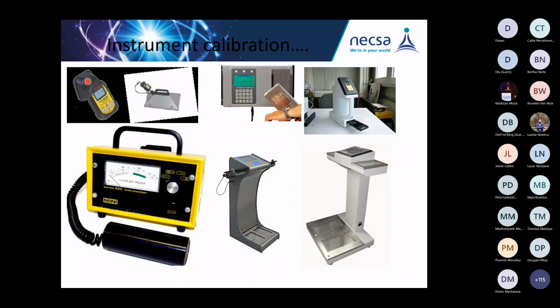This instrument is actually 2-in-1. It can measure surface contamination, alpha and beta, where the unit will be becquerel per square centimeter. Or it can measure the radiation, where the unit will be microsievert. So this is the contamination. It measures becquerel per square centimeter. It measures surface contamination.